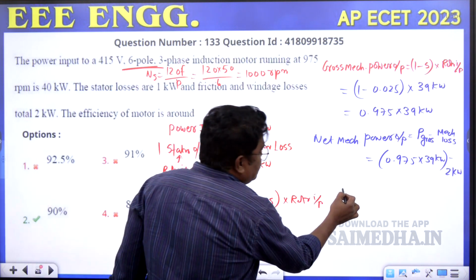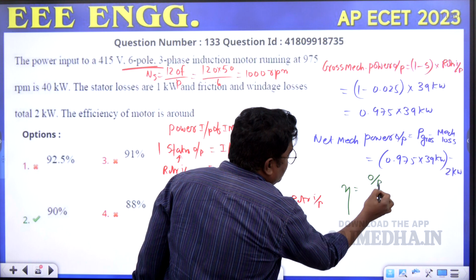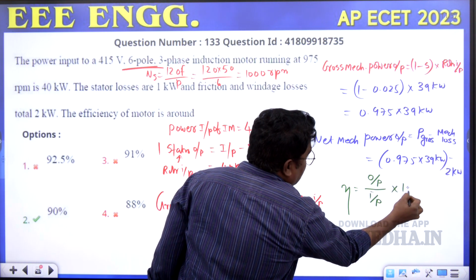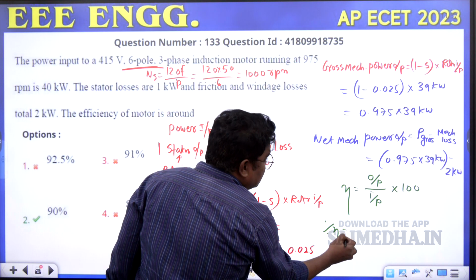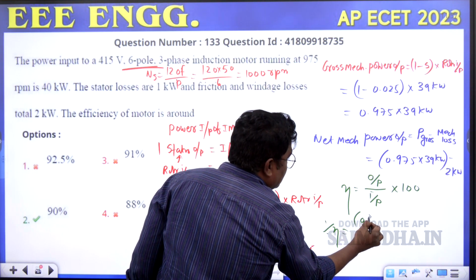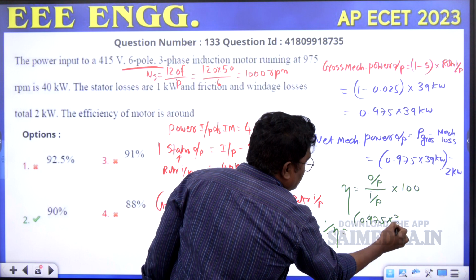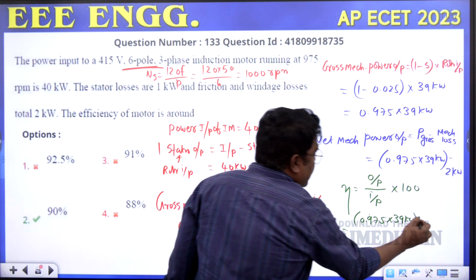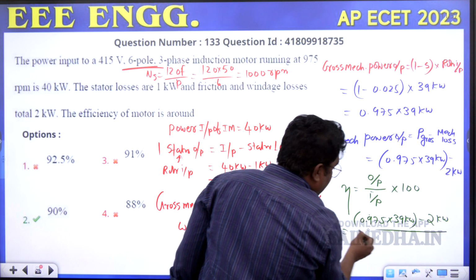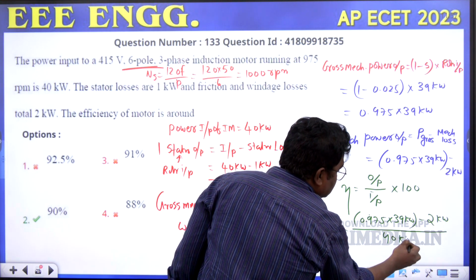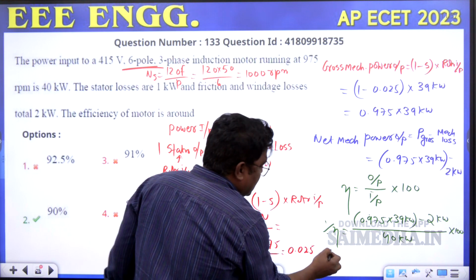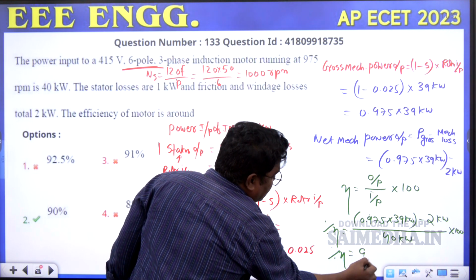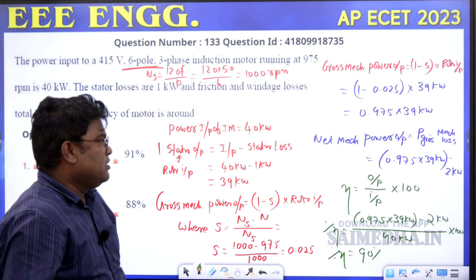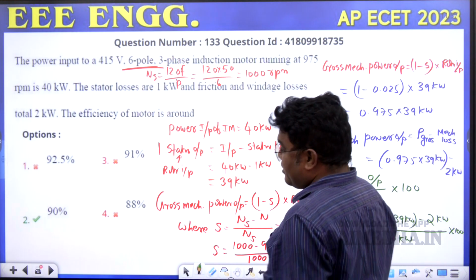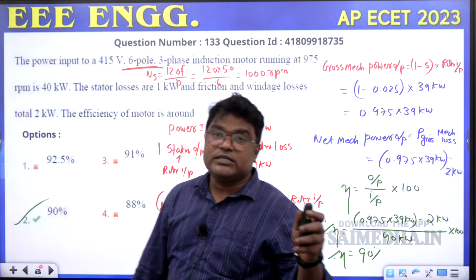Now we require the efficiency of the motor. How do we get the efficiency? The net mechanical power output divided by the input power, multiplied by 100. So percentage efficiency is equal to (0.975 into 39 kilowatts minus 2 kilowatts) divided by 40 kilowatts, into 100. By solving this, you get approximately 90% efficiency. So the answer for this question is 90%, option 2 is correct.